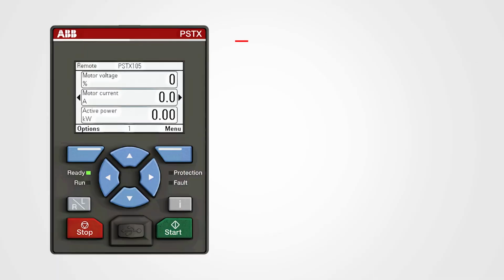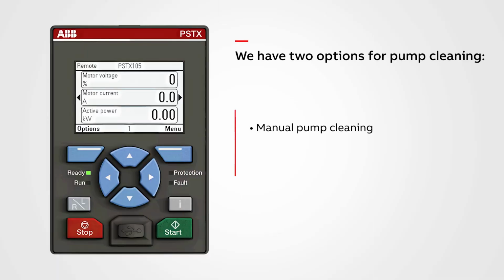We have 2 options for pump cleaning: manual and automatic pump cleaning. In manual mode, the user controls the motor direction by activating forward and reverse pump cleaning commands through the HMI, hardware IOs, or the field bus. In automatic mode, the soft starter starts the pump cleaning sequence when the automatic command is activated and stops when deactivated. During automatic pump cleaning, the motor rotates in a backward and forward sequence.